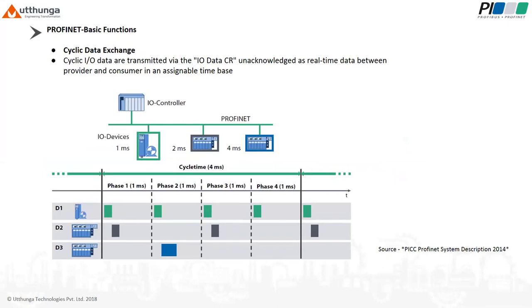Cyclic data exchange. Cyclic data are transmitted via the IO data communication relation. The last topic was that communication relation, the IO data communication relations. The cyclic data exchange is nothing but PROFINET real-time communication within the range of 250 microseconds to 512 milliseconds. Cyclic data exchange can be realized with standard Ethernet controllers and takes place without any TCP/IP information, that is, directly to layer 2. That's why we are getting 100 Mbps speed and real-time communication. We are skipping directly to layer 2.